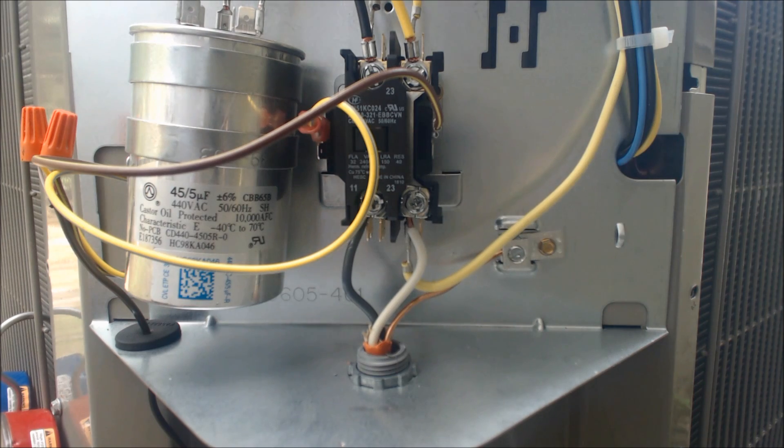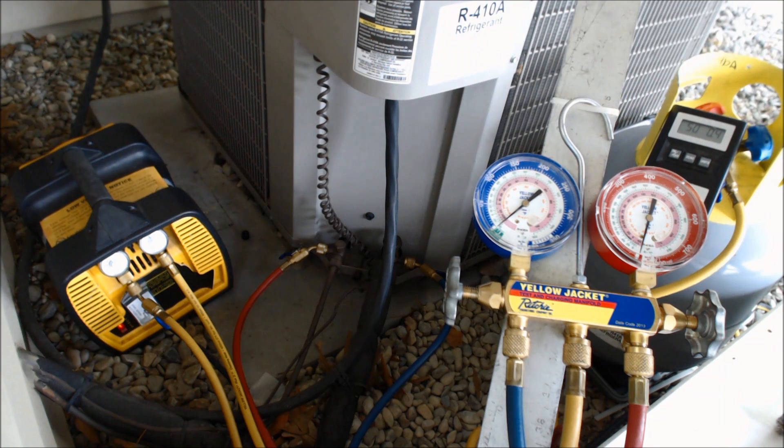I'm going to give you a quick overview of the electrical wiring inside of the condenser. Between zero and seven inches Hg, we poured in about a pound, pound and a half of refrigerant. This unit has 12 and a half pounds of refrigerant total, so that just tells you there's quite a bit of refrigerant even below zero in the inches Hg.